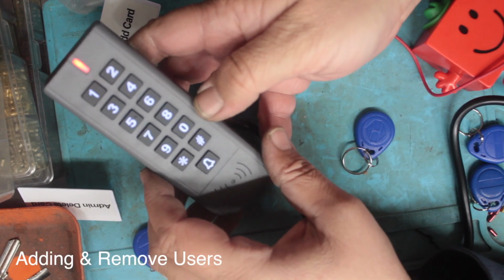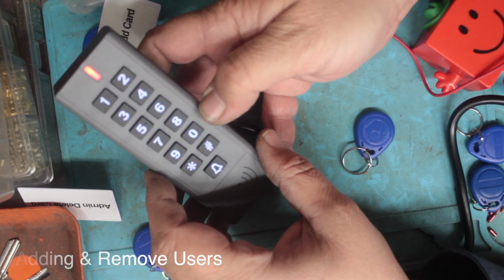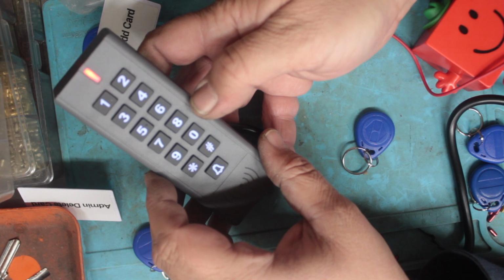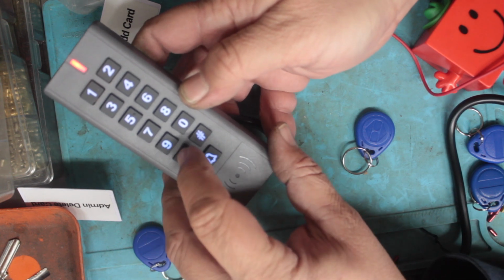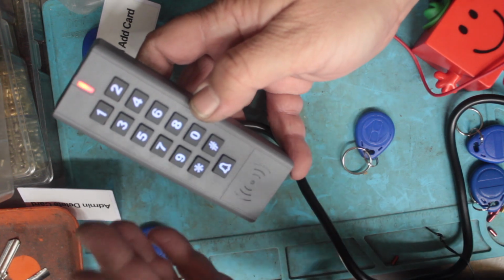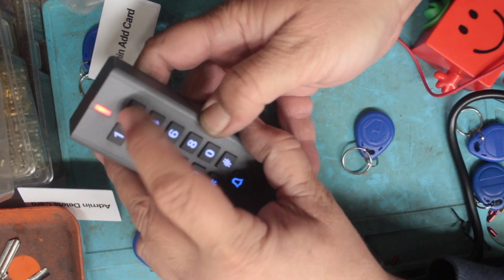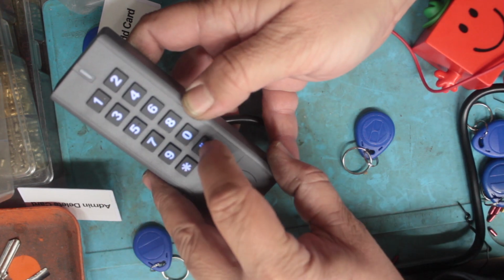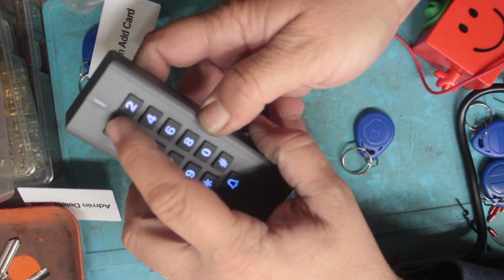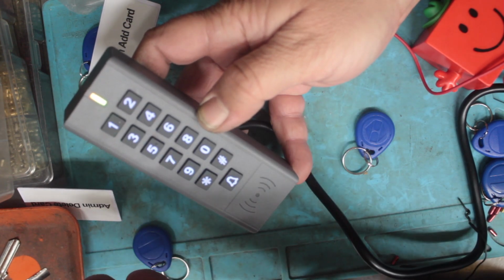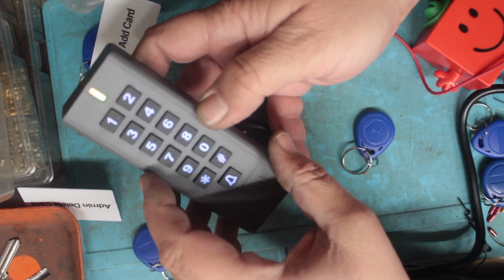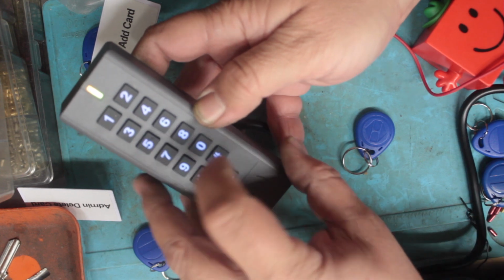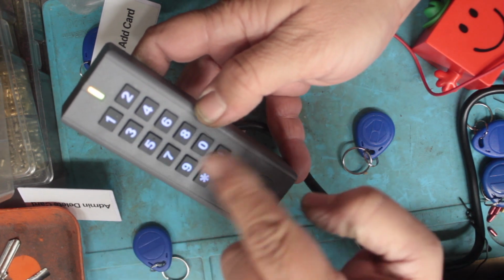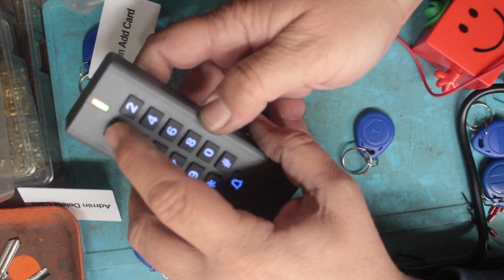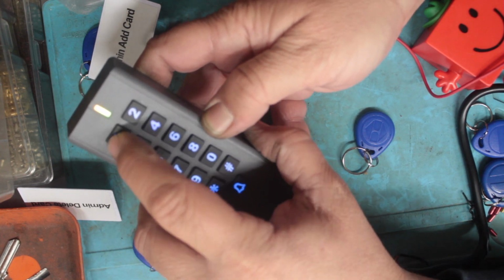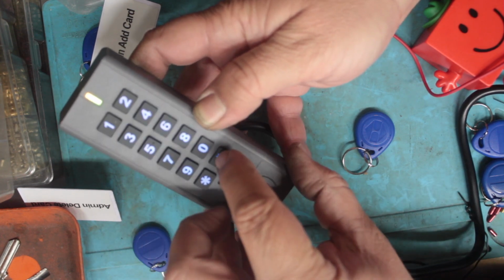Okay, now we're going to perform the simple task of adding and deleting a user and assigning it a user position. So we push star, we put in our master pin number 1 2 3 4 5 6 hash. We want to add, so we go 1 for add. Now we give it an actual position, and for this position I'm going to go 55, hash. Now I can put in my code between 4 and 6 digits. 1, 2, 1, 2, 1, 2, hash.